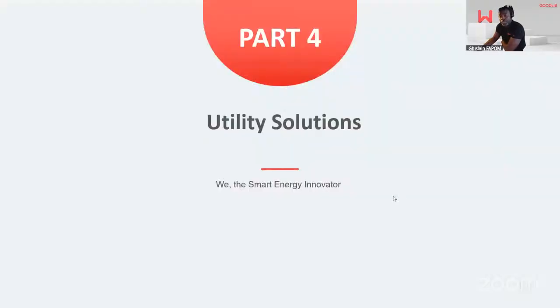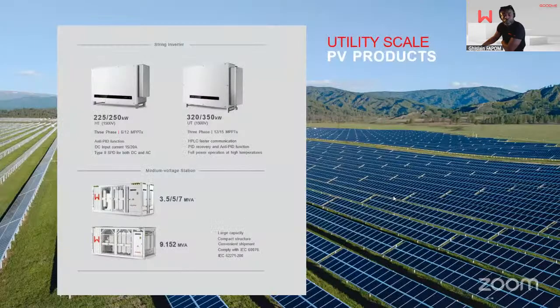Now, the utility solutions that we have, that will be very quick. We have two platforms, the 225 and 250 kilowatt at 1500 volt DC and 800 volt AC, and then the bigger platform, 320 to 350 kilowatt, 1500 volt DC and 800 volt AC. This inverter has PID recovery and anti-PID, meaning it can have PID recovery for 24 hours: anti-PID works during the day, and PID recovery works during the night. They are adapted for high current modules, the new generation modules. They all have type 2 SPD, on both DC and AC sides.